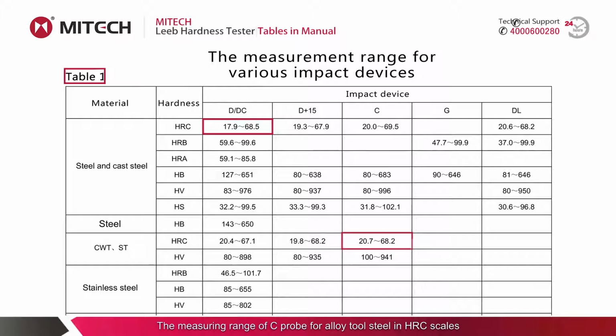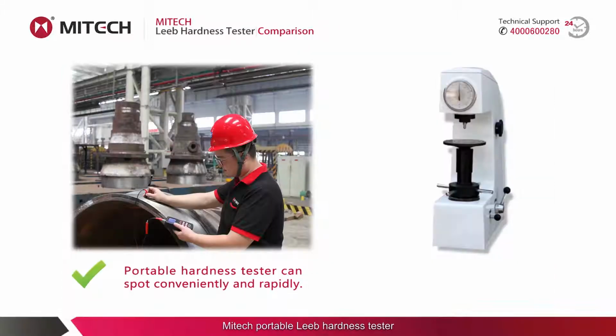The measuring range of the C probe for alloy tool steel in HRC scales is 20.7 to 68.2. Please refer to the table for the corresponding hardness units, corresponding materials, and probe range. For example, if measuring the HRC value of steel and cast steel with a G-type probe, it won't work because the related table entry is blank. According to relevant international standards, there is no specific scope. Thus, that's a normal phenomenon.